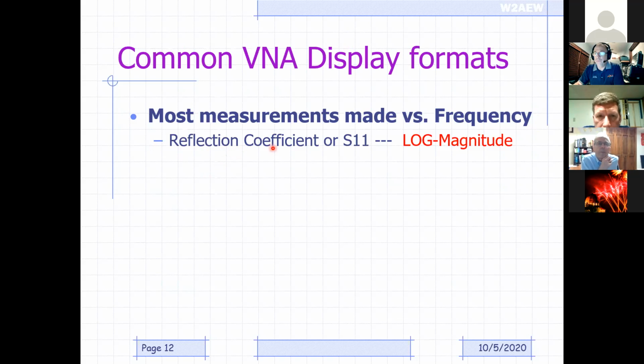So the reflection coefficient, or S11, again, that's that A over R measurement. Most often, if we're not looking at phase, we're just going to look at the magnitude of it. We actually use a log magnitude display, like most spectrum analyzers do. Okay, and the reason for that is it gives us a lot of dynamic range on the screen. It's easy to see something that's 50 or 60 dB down on a log magnitude display. That would be very, very tough or impossible to see if it was a linear scale.